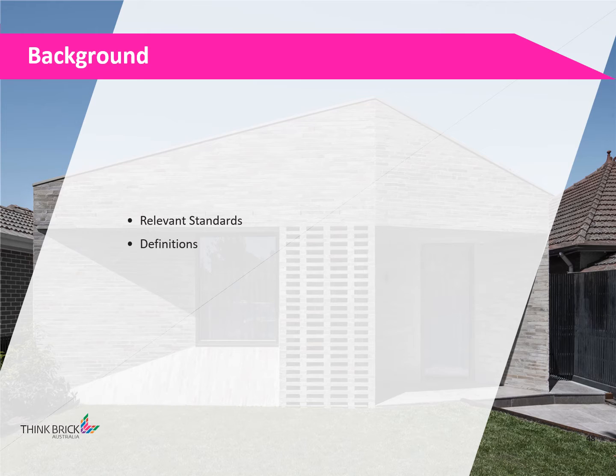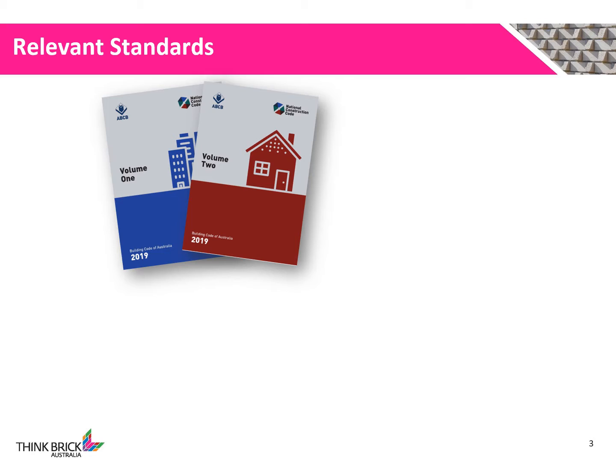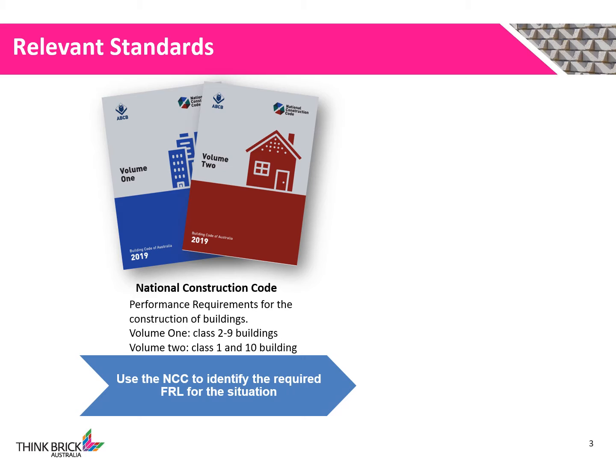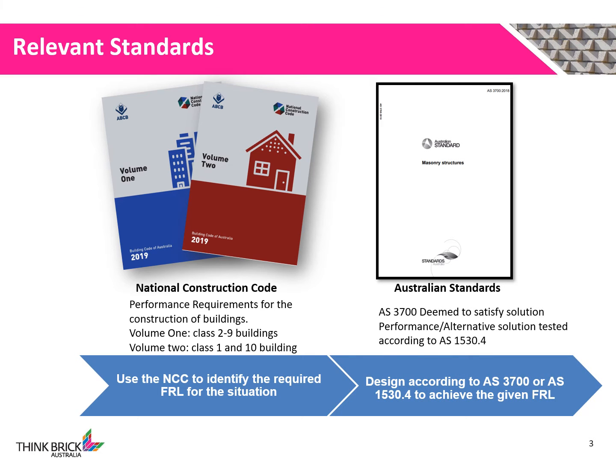Before we dive into our presentation, we're going to look at some background information that will be of use — these being the relevant definitions and standards for FRL design. NCC volumes 1 and 2 are used to identify the required FRL for a given application. Volume 1 covers building classes 2 to 9 and volume 2 covers building classes 1 and 10. AS 3700 outlines the design procedures used to achieve the required FRLs from the NCC. We will not be covering the use of AS 1530.4, which covers performance and alternative solutions to FRL designs in this presentation.